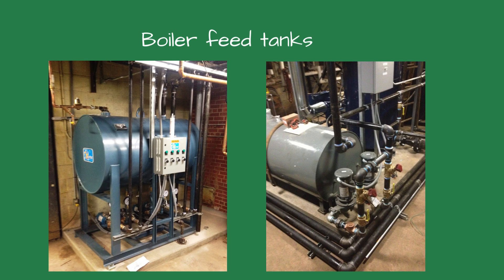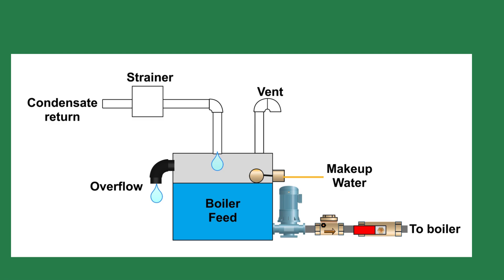The boiler feed tank is about five times larger than a condensate tank. Inside the tank is a float valve that feeds make-up water to the system. The float valve is set to maintain the water level at about one-third the tank height. The cold make-up water is then chemically treated and warmed by the returning condensate, so cold water is not injected into the hot boiler.